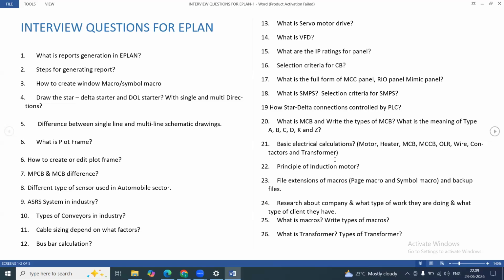Actually, according to the standard, if we are using current sensors for long distance, the cable length can be more. So exactly 0 to 4 milliampere, we consider whether our sensor is working properly or not. If a signal below 4 milliampere is coming, it means our sensor is not working properly, or even the insulation we have in our cable is not working properly. Or we can say that if a 0 milliampere signal is coming, the cable can be damaged.